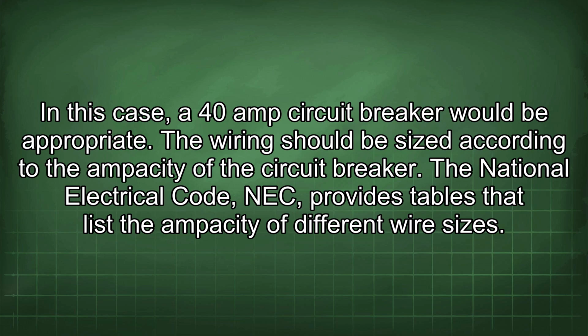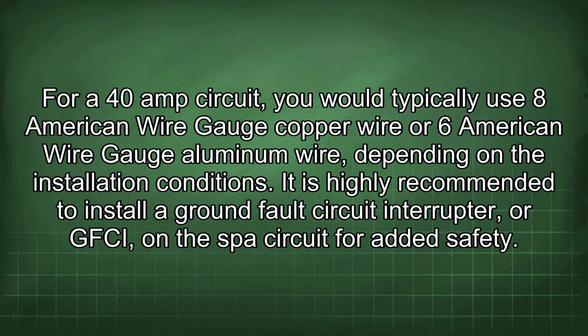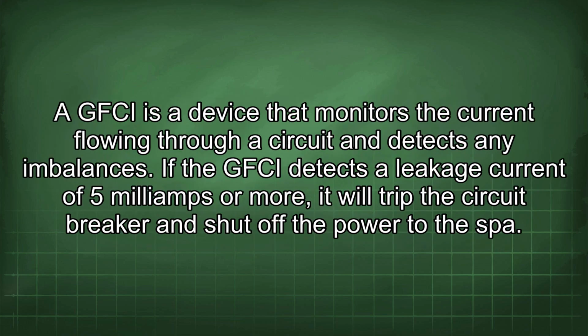The wiring should be sized according to the ampacity of the circuit breaker. The National Electrical Code, NEC, provides tables that list the ampacity of different wire sizes. For a 40-amp circuit, you would typically use 8 American wire gauge copper wire or 6 American wire gauge aluminum wire, depending on the installation conditions. It is highly recommended to install a ground fault circuit interrupter, or GFCI, on the spa circuit for added safety. A GFCI is a device that monitors the current flowing through a circuit and detects any imbalances. If the GFCI detects a leakage current of 5 mA or more, it will trip the circuit breaker and shut off the power to the spa.